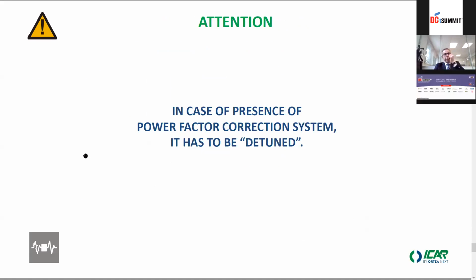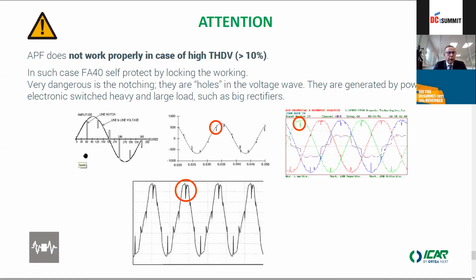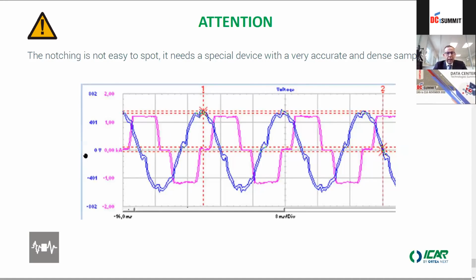If you have a power factor correction system present in the line and you have to add an active filter, the PFC must be detuned to avoid the harmonics burning the capacitors. I think my time is quite finishing, and these are some advices.